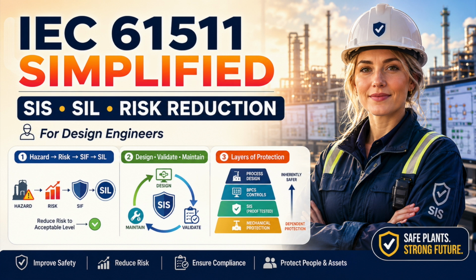The engineering manager cannot treat functional safety as one specialist package. It touches process design, piping and instrumentation diagrams, control architecture, electrical power, shutdown valves, vendor packages, software, construction, commissioning, operations and maintenance. Timing matters as much as technical detail. If the SIL assessment is completed after equipment purchase, the project is already constrained. If the safety requirement specification is issued after logic development, the sequence is wrong. If proof testing is discussed after startup, maintainability has already been compromised. The life cycle has to be integrated into the project plan from the beginning.